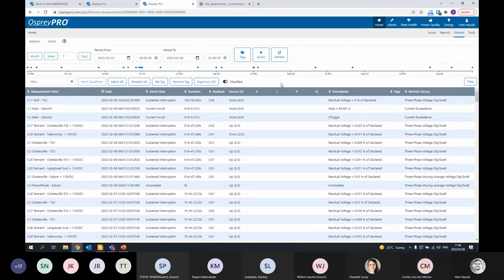Okay, so the next session in March will be on the installation and commissioning of the VECTO 3 devices. That would be using Osprey Lite to do the commissioning, but also using the web interface, which we prefer going forward from here. And then how to commission that device on Osprey Pro - how to get the instrument on Osprey Pro, attach the instrument to the measurement point, and set up the configuration to start recording the correct data that you want. There will also be detail on how to install instruments for different applications.